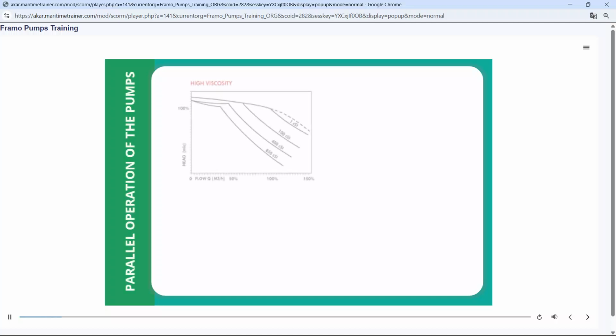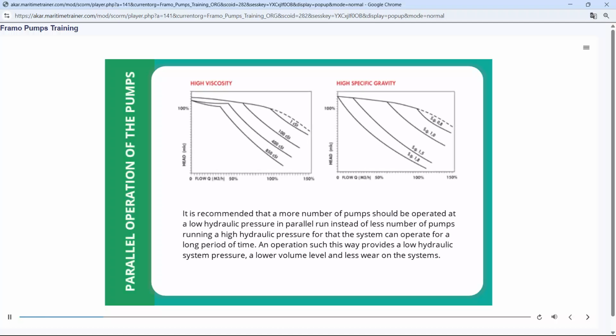It is recommended that a greater number of pumps be operated at a low hydraulic pressure in parallel run, instead of a smaller number of pumps running at a high hydraulic pressure, so that the system can operate for a long period of time. Operating this way provides a low hydraulic system pressure, a lower noise level, and less wear on the systems.